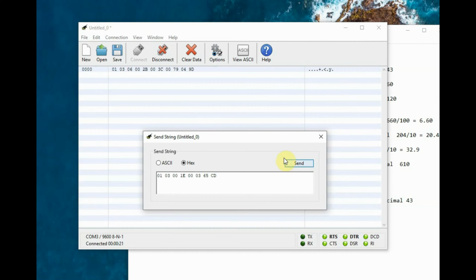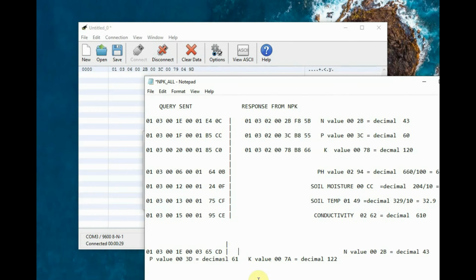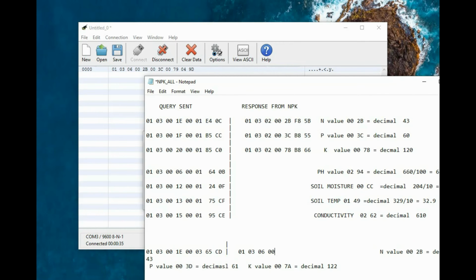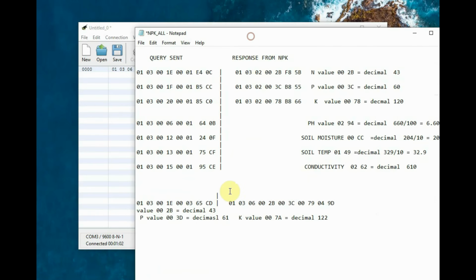Now click on send and you get the data back. It reads the register data starting from address 1E, reading a total of 3 registers, that is the NPK values. We are sending data 01, 03, 001E, and then 0003, that is a total of 3 registers we read. Finally we get the value as 0103; 0006 is the total number of bytes following.